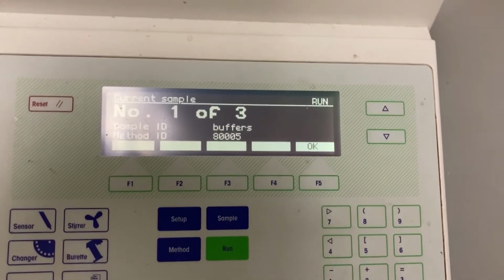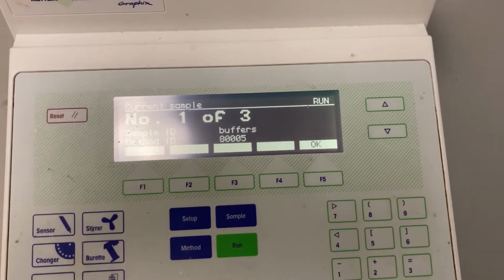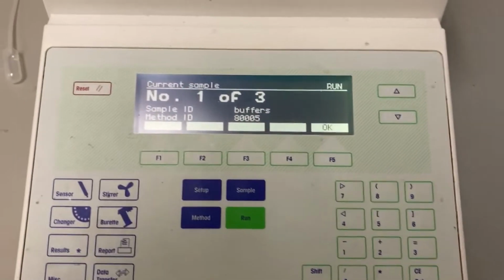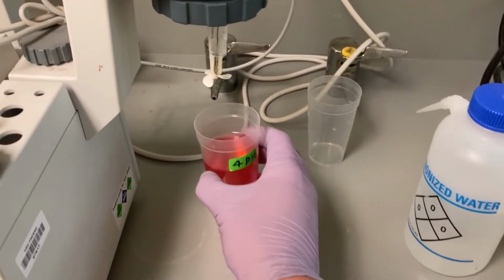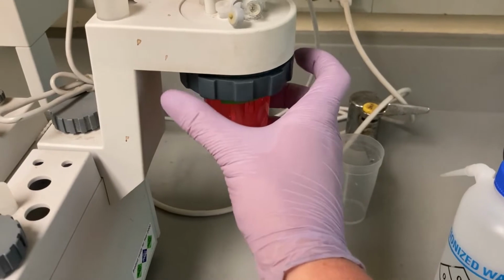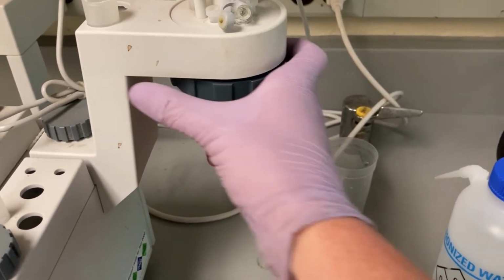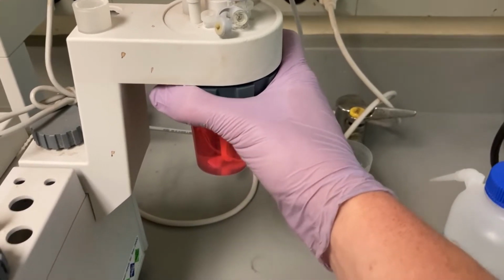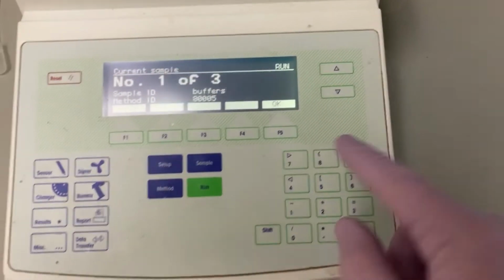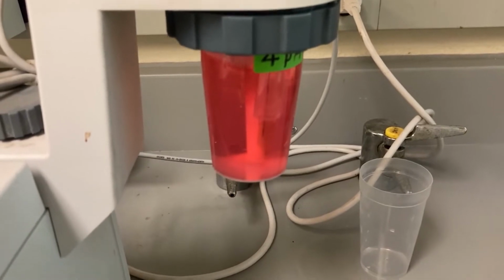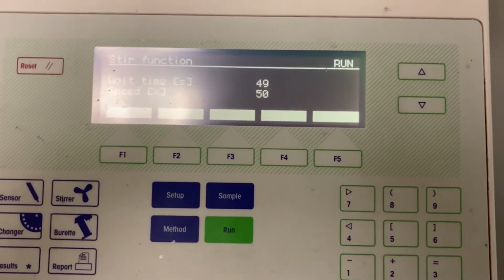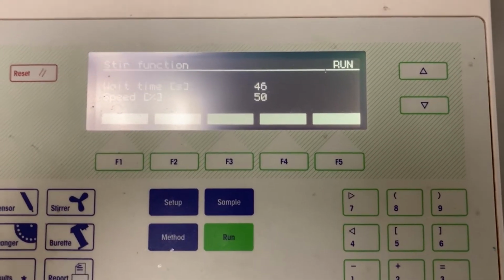So now that we're ready to calibrate, you'll see this page, this menu. The calibration order is always 4, 7, 10. So it's expecting the 4 pH buffer first. So to put these in, you just press up, you'll feel it click, and then tighten the gray nut by turning it counterclockwise. And once it's secured, you can hit OK. And you'll see the propeller inside of the cup start to spin. And each time you calibrate for each pH buffer, it takes 1 minute.